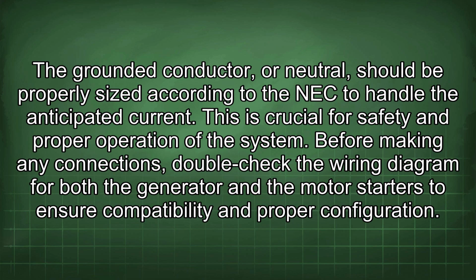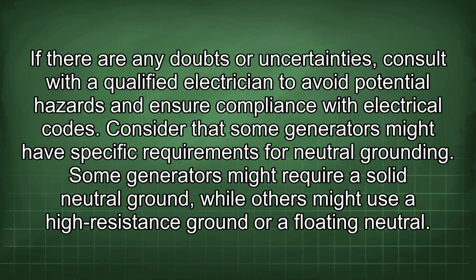Before making any connections, double-check the wiring diagram for both the generator and the motor starters to ensure compatibility and proper configuration. If there are any doubts or uncertainties, consult with a qualified electrician to avoid potential hazards and ensure compliance with electrical codes. Consider that some generators might have specific requirements for neutral grounding.